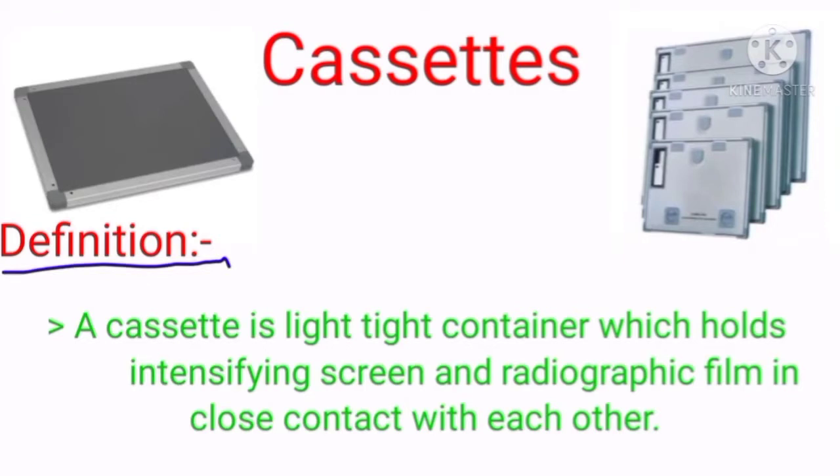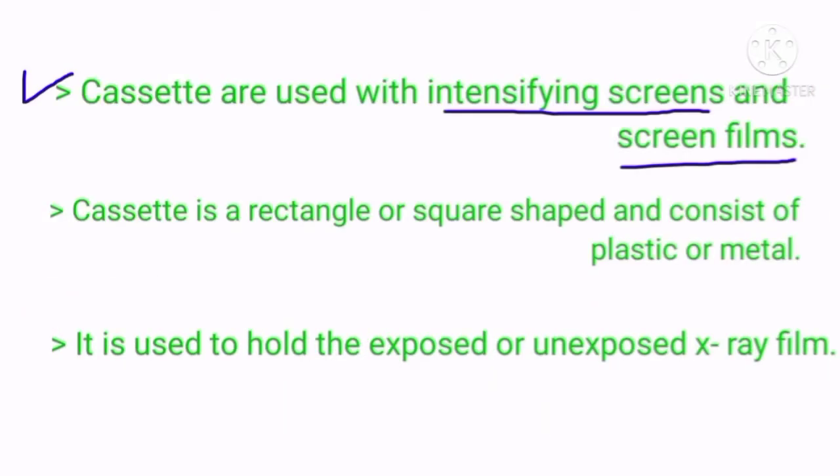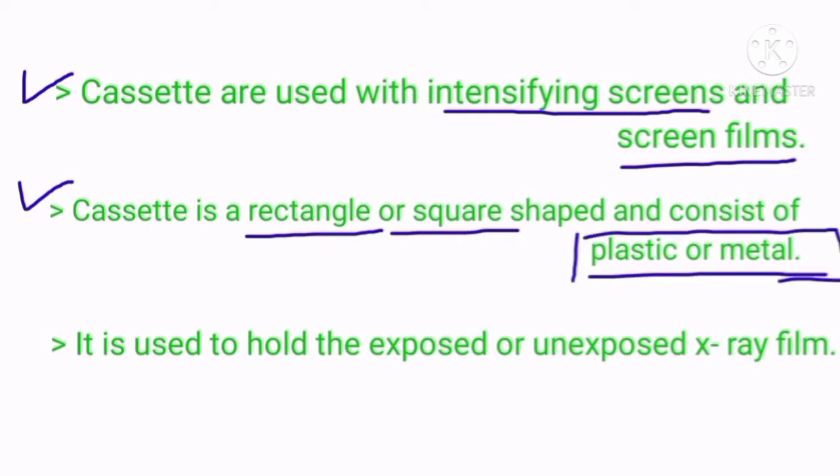What is a radiographic film cassette? A cassette is a light-tight container which holds intensifying screens and radiographic film in close contact with each other. Cassettes are used with intensifying screens and screen films. They are rectangular or square shaped and consist of plastic or metal used to hold the unexposed or exposed x-ray or radiographic film.